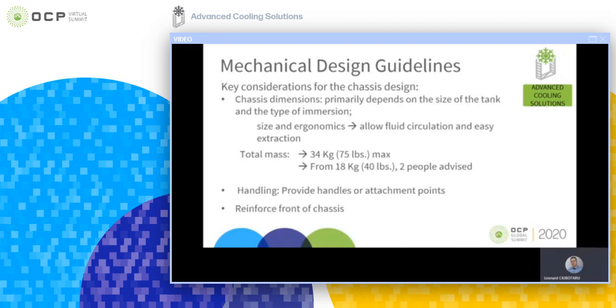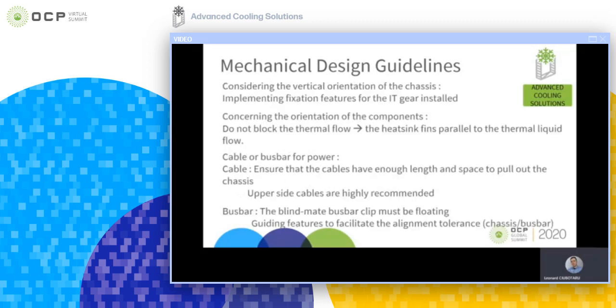If the server is more than 18 kilograms or 40 pounds, it is recommended to be handled by two people. For permitting easy handling, the chassis needs to be equipped with handles for manual manipulation or otherwise with some sort of attachment fixture for mechanical manipulation. As a difference from the rack servers, we recommend paying special attention to the mechanical resistance of the front side of the chassis, where the vertical pulling forces will be applied, and reinforce this part accordingly.